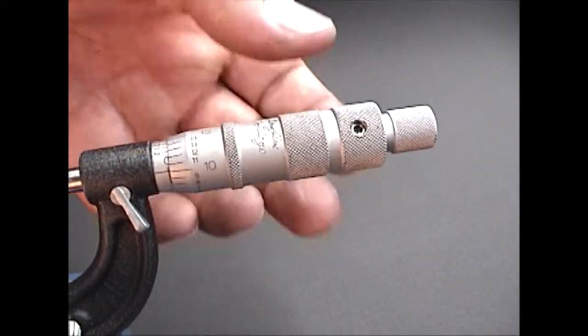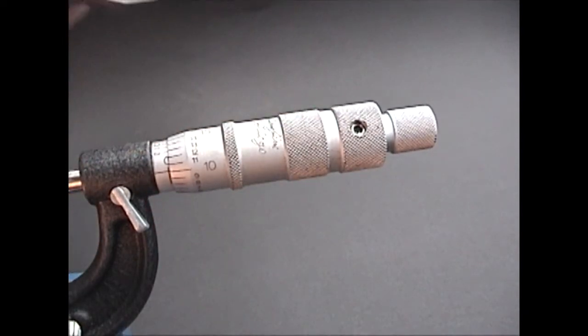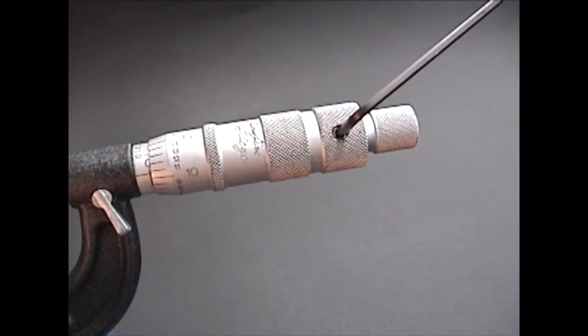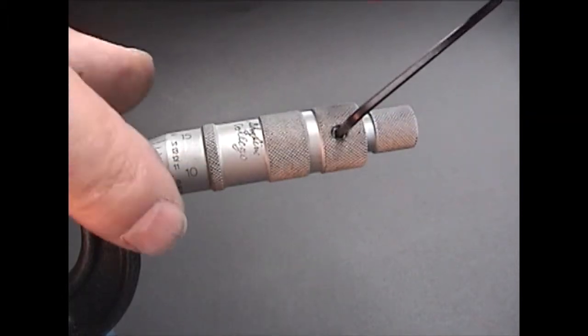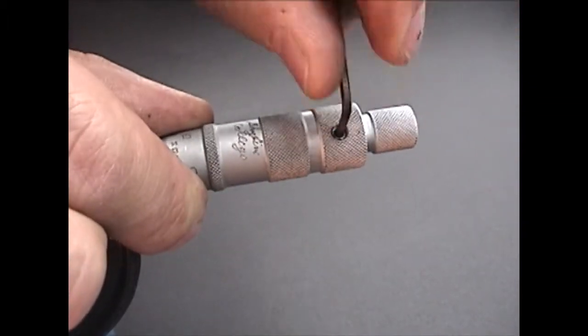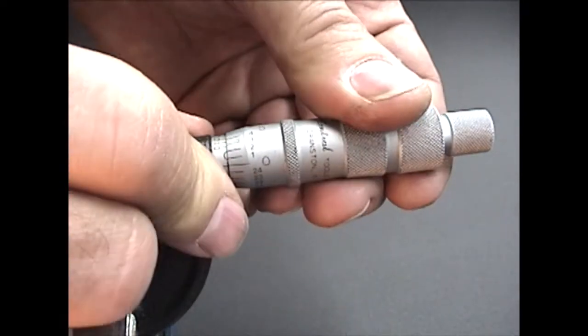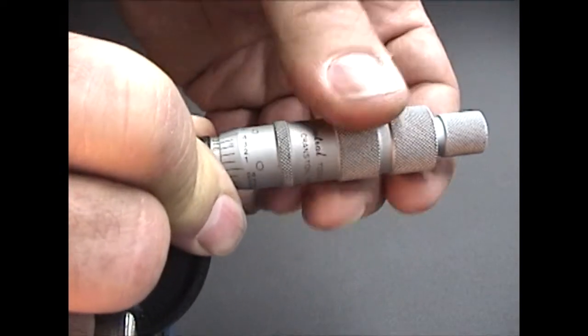If adjustment is needed, an allen set screw can be found on the thimble near the thumb ratchet. Loosen the set screw with the allen wrench. Now the thimble will move freely on the barrel.